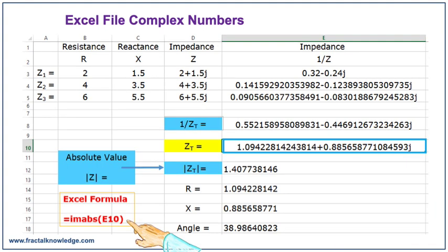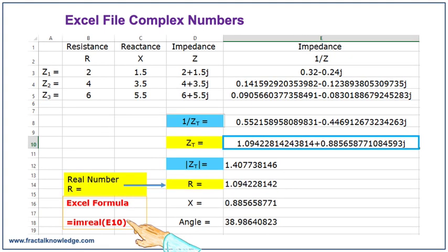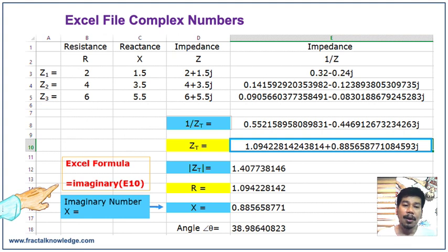Now to get the absolute value of that impedance which we can use in the calculation of short circuit, the formula that we can use is equals IMABS, open quantity, move the cursor to E10 the impedance, close quantity, enter. We've got the value of the absolute impedance Z 1.4077 ohms. You can just copy the R value and the X value from the complex number, but you can see we have also Excel formula for that. We can use equals IMREAL E10. For the reactance, the Excel formula is equals IMAGINARY, open quantity E10, close quantity, enter.